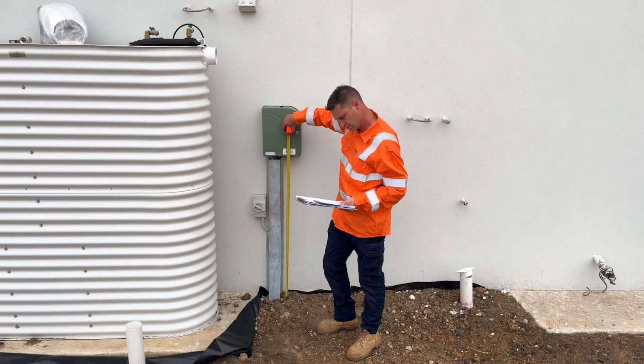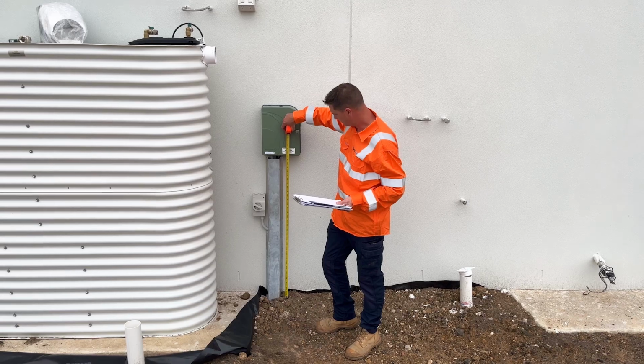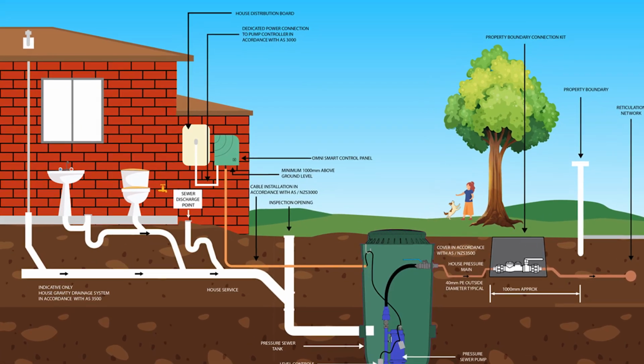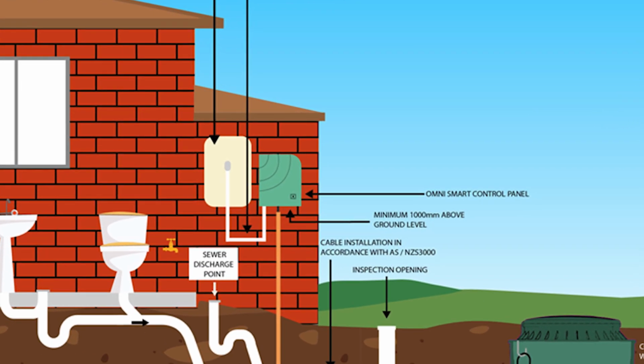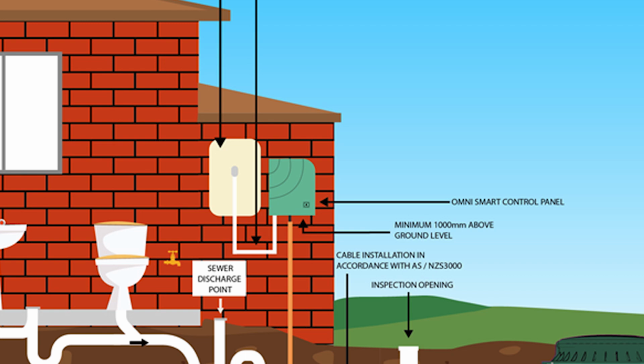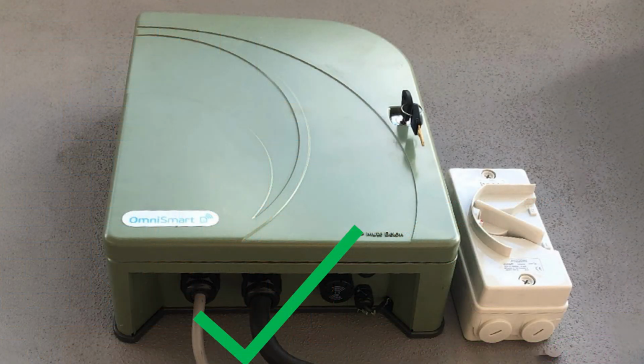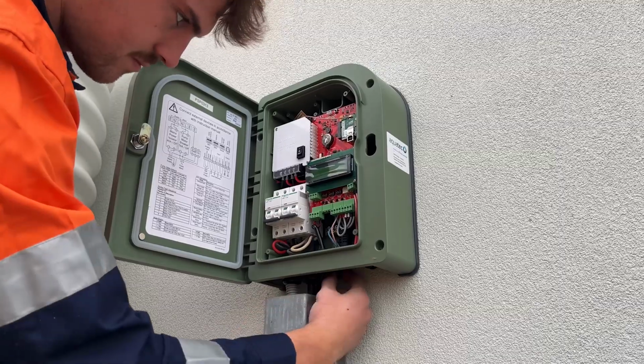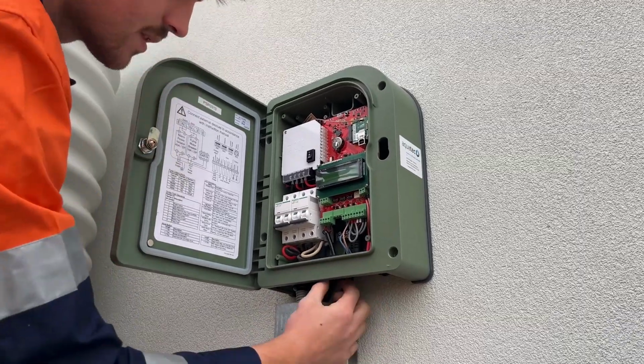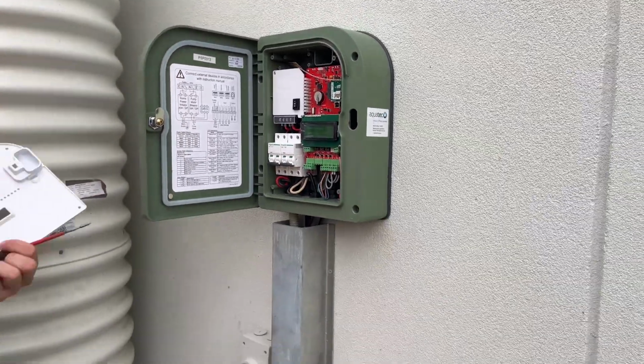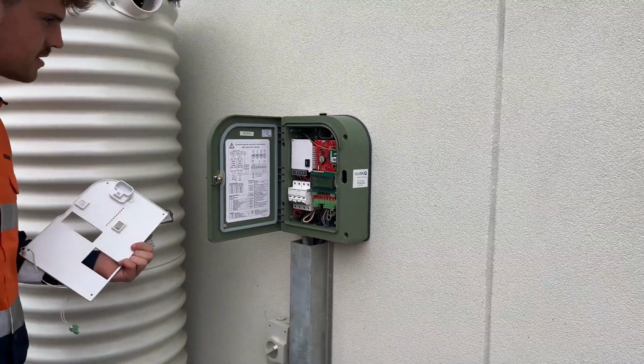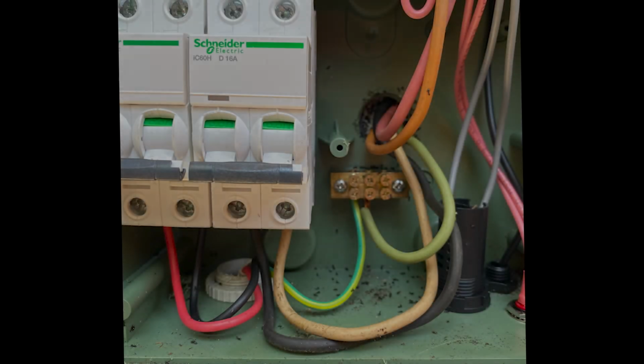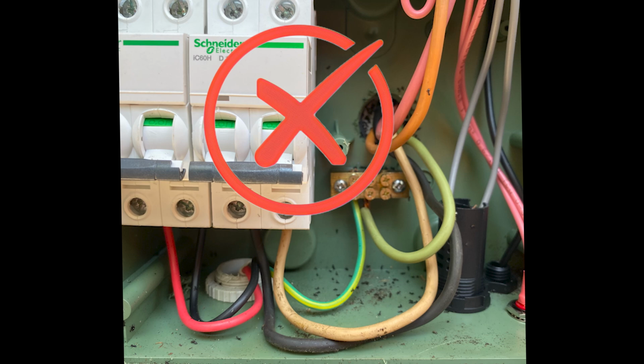The control panel itself needs to be fixed properly to either a wall or a post. Electrical conduits need to finish approximately 100 millimeters below the control panel base. Then, to enter the control panel with cables, you must use cable glands and only enter via the base of the control panel. Each cable will require a separate cable gland. No other entry point into the control panel for cables is acceptable, and failing to follow this step will void warranty.